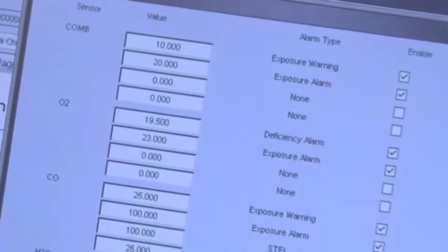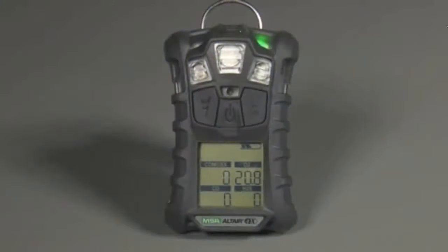Instrument setup pages and MSA Link software are used to change alarm set points and to disable certain alarms. Please refer to the Altair 4X multi-gas detector instruction manual for more information regarding alarm setting changes. When in Measure Mode and enabled, MSA's green safe LED feature flashes every 15 seconds when all of the following conditions are met.